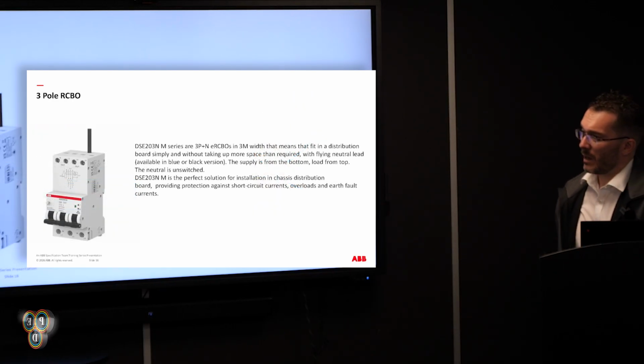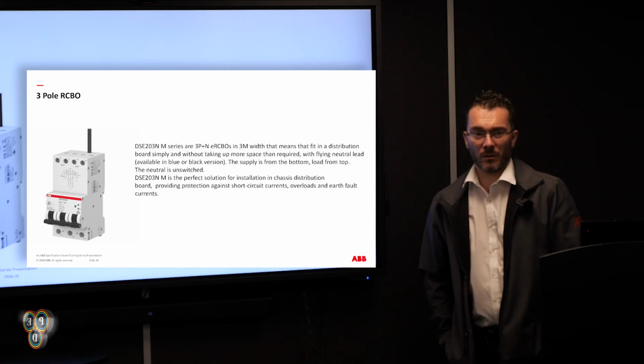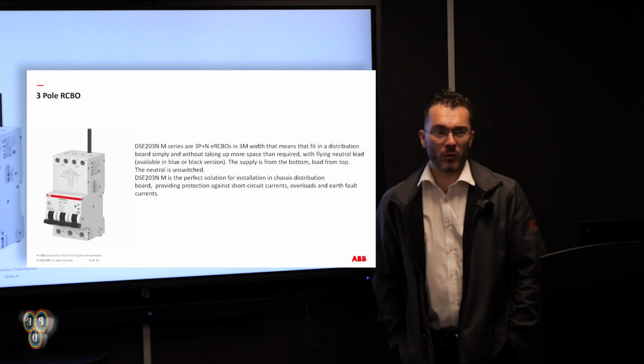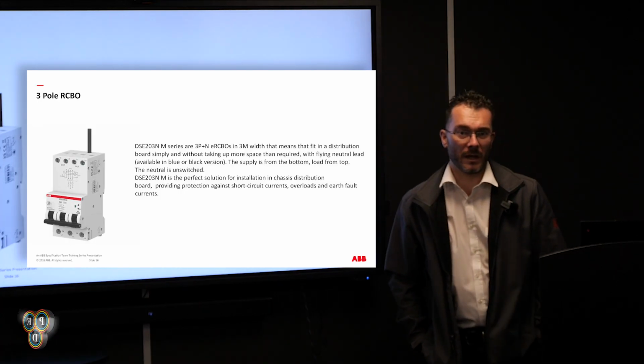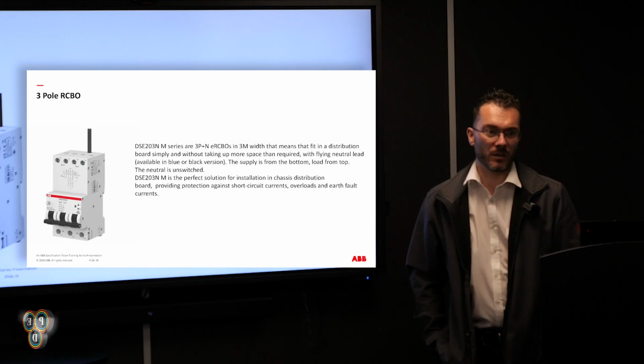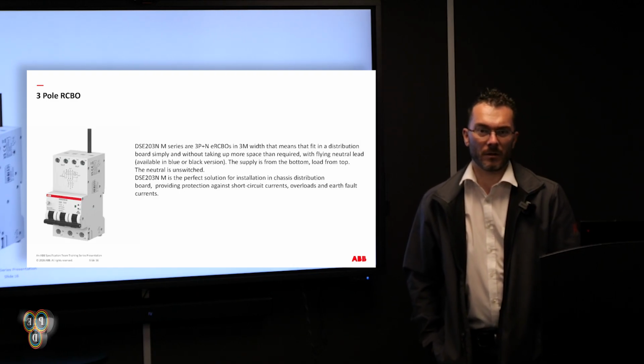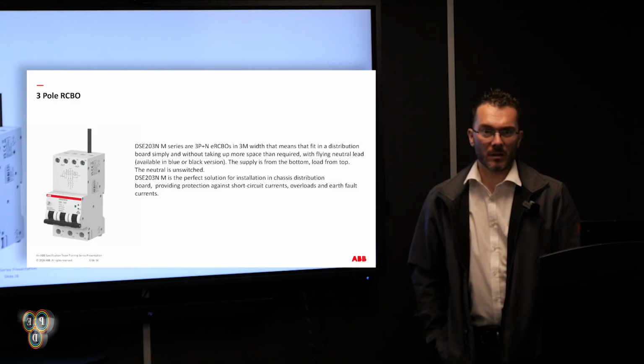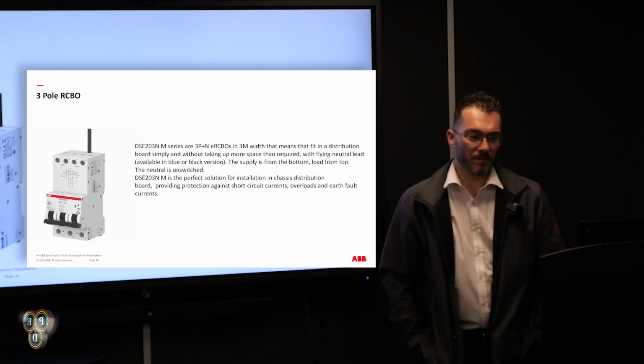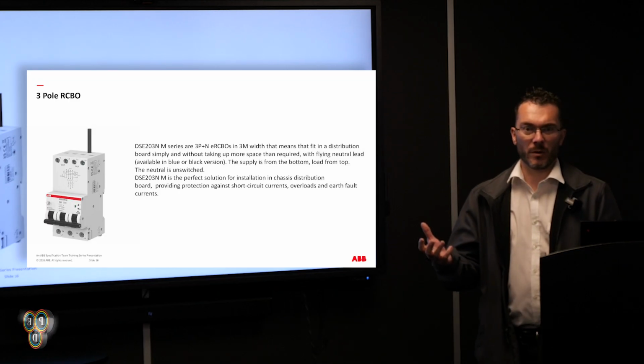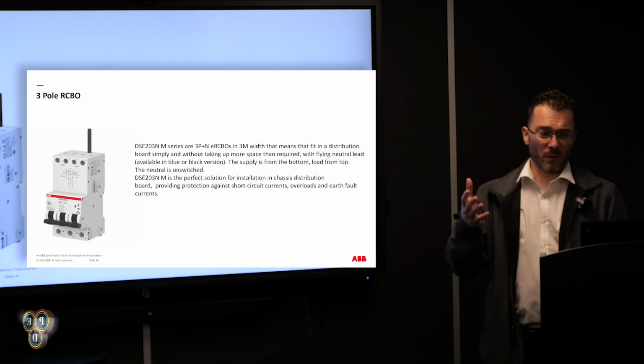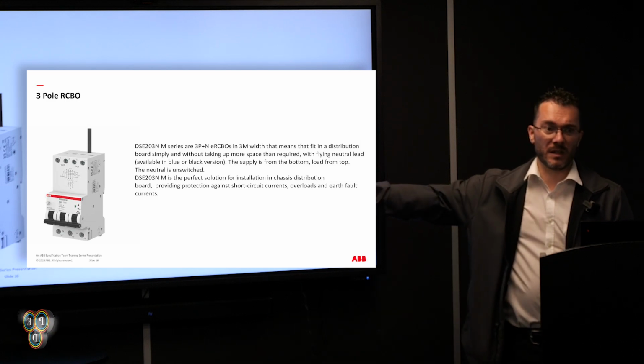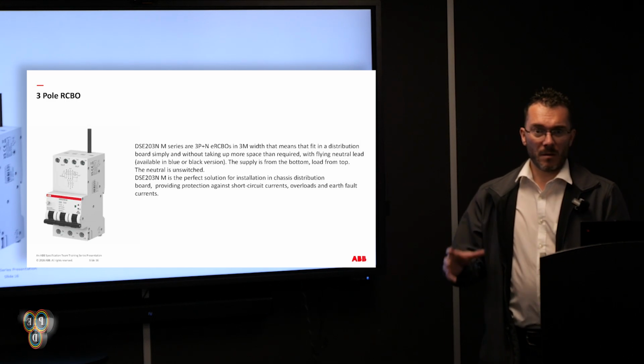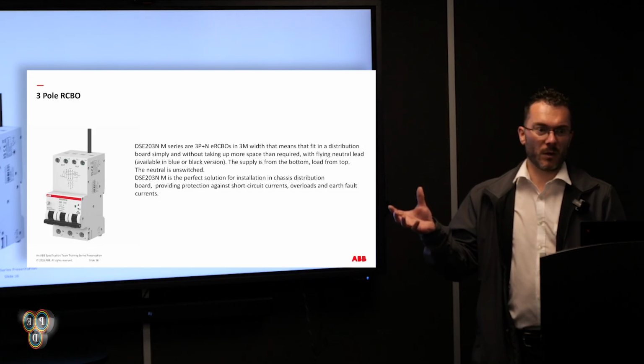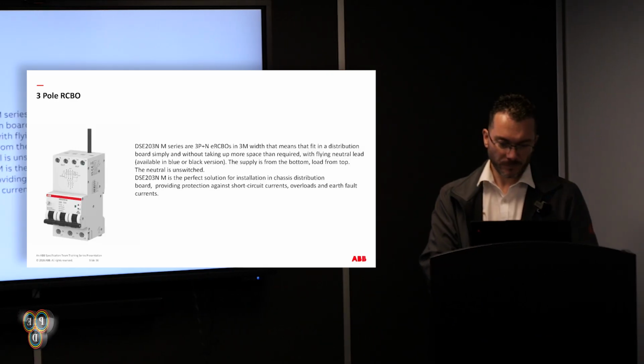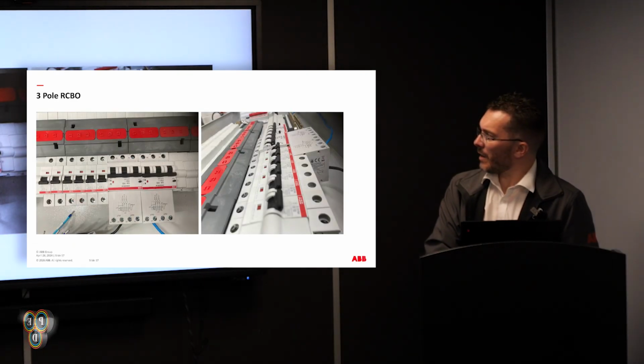We have, however, released a triple pole RCBO, for those that you may or may not use. It is 3 modules wide and fits directly into the distribution board. There's no Vigi units or anything like that. That is up to 63 amps. So if you're working on commercial kitchens, ground source or air source heat pumps, things like that, 3-phase circuits that require RCBOs, we've got that option there. Again, it reduces the size of distribution boards. I know some of the competition use Vigi units. We have got a Vigi unit solution, but it doesn't fit within our distribution boards, so we've released this to counteract that. If you're using competitors, you're going to lose 6 ways by converting one of the MCBs into a Vigi unit. Just an example there of how they mount within the board.